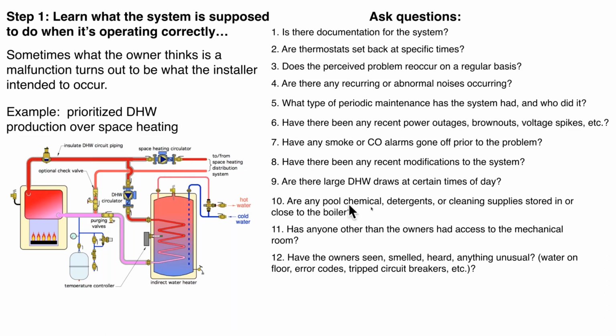Here's one that's interesting. Pool chemicals, chlorine, detergents, cleaning supplies, anything that has chlorine in it that's stored in proximity to an atmospheric boiler is a real problem. That chlorine vapor can go into the combustion chamber and create hydrochloric acid, severe corrosion. So you do not want to store pool chemicals, detergents, or cleaning supplies in a mechanical room. And yet I've walked into many mechanical rooms that simply because there's space there and people don't frequent them, that's where the pool chlorine tablets get stored and so forth.